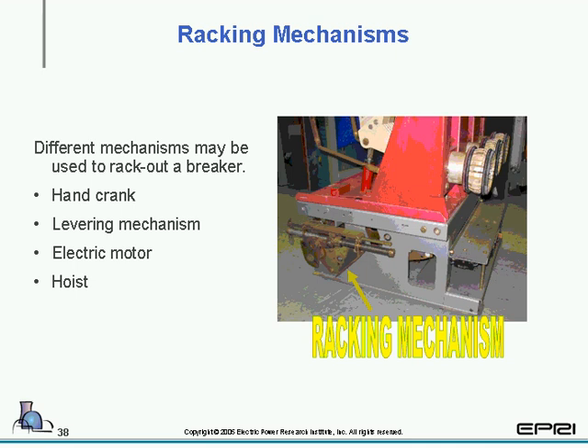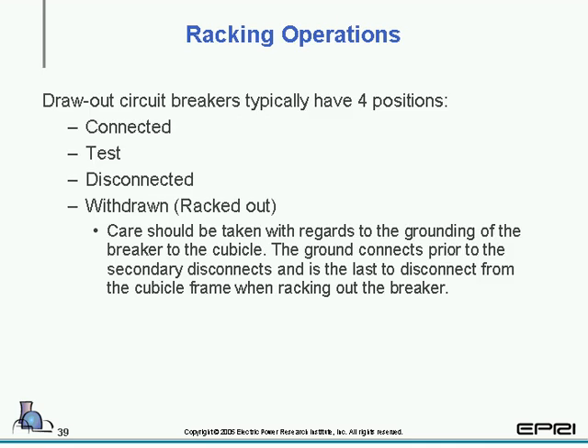And that pretty much concludes fixed breakers. Now the next major group is racked breakers, or racking type breakers, and that's done with a racking mechanism. And there are different racking mechanisms that may be used to rack out a breaker: hand crank, levering mechanism, electric motor, and hoist. And you can see this particular design has a racking mechanism bolted to the breaker itself. Some are actually associated with the switchgear and not the breaker.